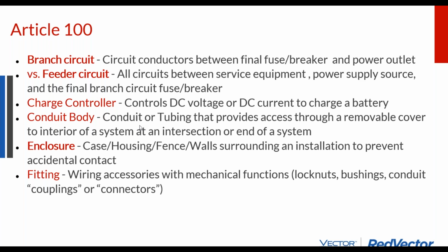Conduit bodies. We have conduit or tubing that provides access through a removable cover. When we think of conduit, we think of PVC conduit or metal EMT conduit. But in fact, there's a wide variety of ways that we can enclose the cables, the actual wires, from point A to point B. That's all categorized as raceways. And conduit bodies are a kind of raceway. So whether it's a tube or a box or a wire, it can trigger a specific term in reference to a specific part.